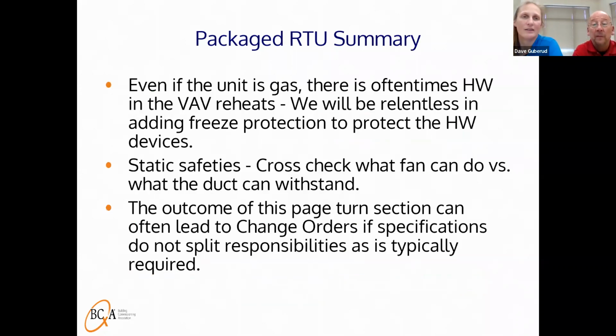Nope, that's perfect. So even if the unit is gas, we feel very strongly that there's freeze protection on units. The placement of that freeze protection is different. As Dave mentioned in the schematic, having it downstream of the air handler or the rooftop unit, because in that case, what we're protecting are the hot water coils in the duct downstream. We've had too many instances where the unit has failed, like the gas went out or something, and they're pushing the cold air down, and you freeze the coils and cause almost more damage.